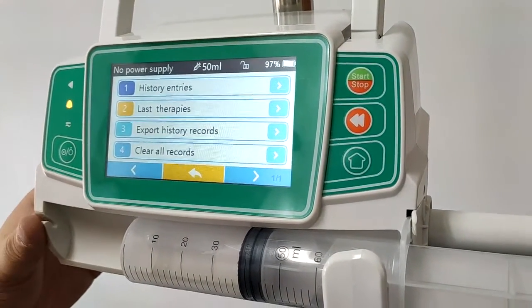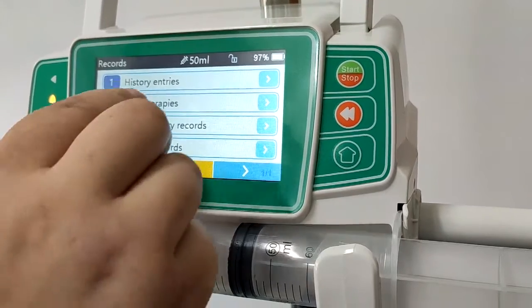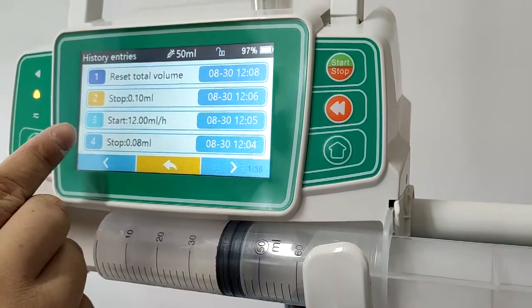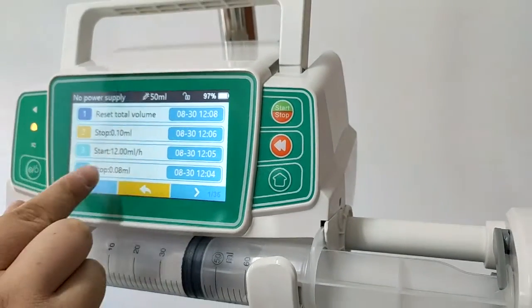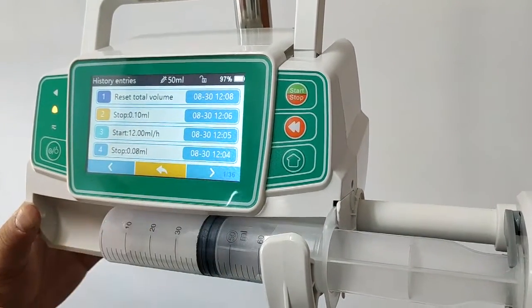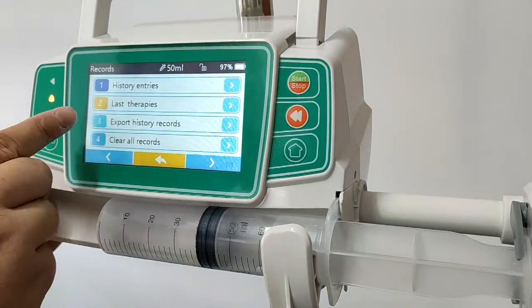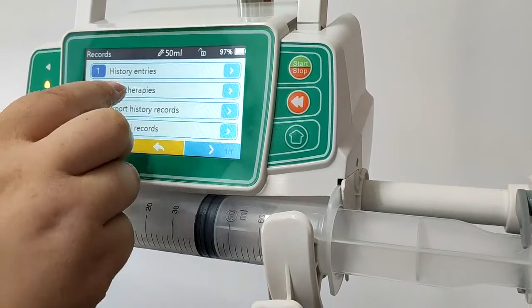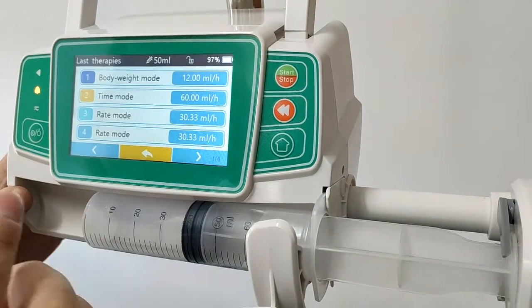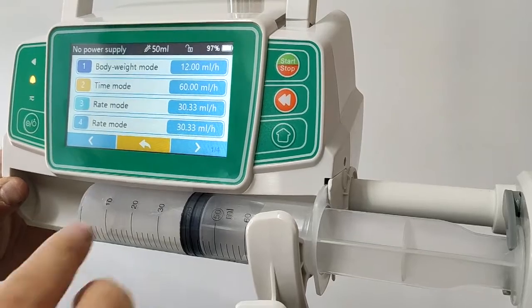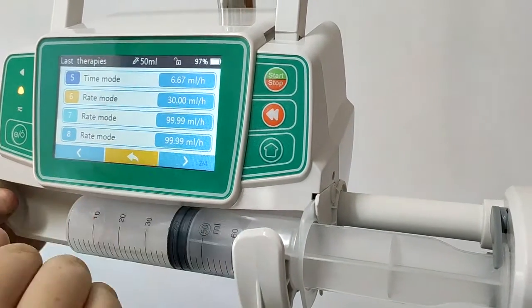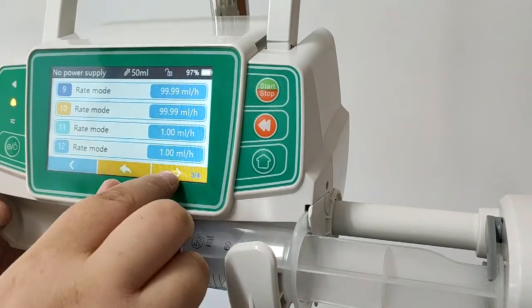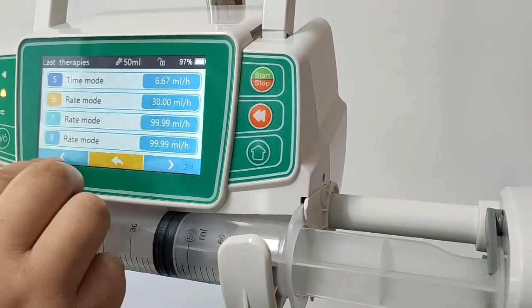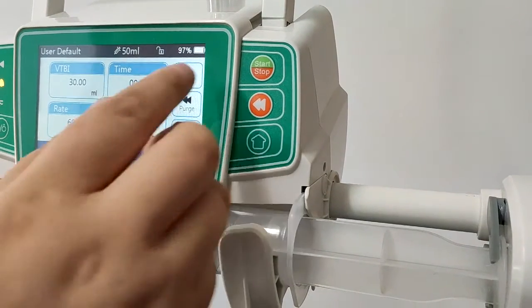Now let's come to the records. Click it and enter it. Our pump has up to 5,000 history entries. You can see the entries will be with the serial numbers and record of what you have done and the time stamp with date and time. And there is another function, last therapy. It means the records of 20 last therapies. If you want to have a faster start after you have stopped the pump, to find a rate or mode you have used before. For example, you want to use the time mode again, and then you click it and then start. Will be very fast to save some time in emergency cases.